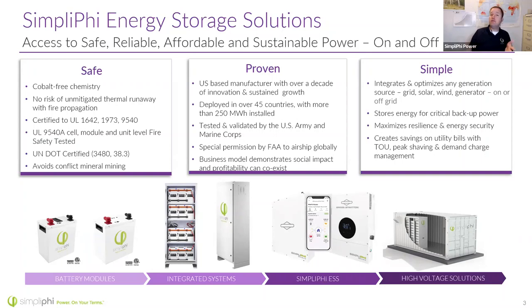I believe this was getting so popular because if you walked over to the Solark booth, they had the Solark 30K and the Solark 60K there - these are three-phase commercial systems that need a much higher battery input voltage. I think the startup battery input voltage on a Solark 30K is like 150 volts DC. We don't let you run our standard Phi and Amplify batteries in series, but these battery racks we provide can be wired in series up to the voltages you need.